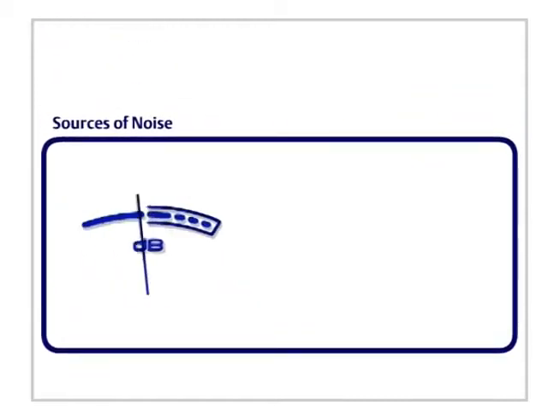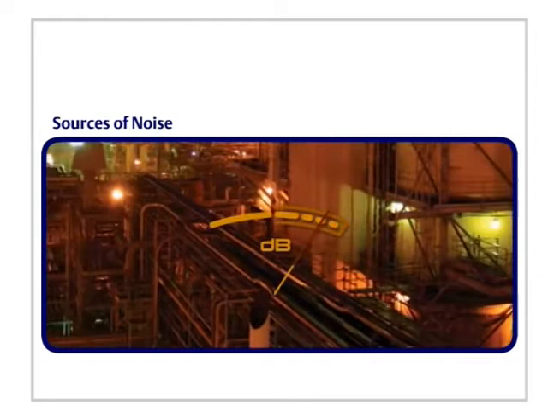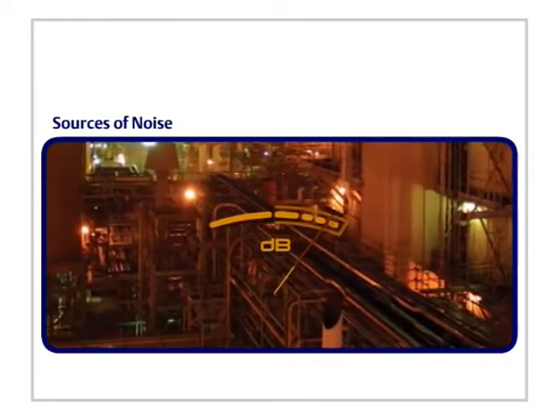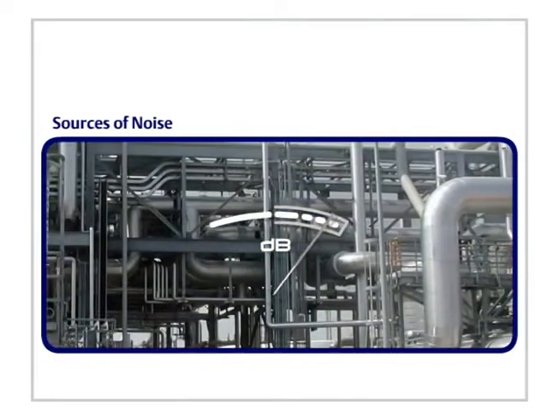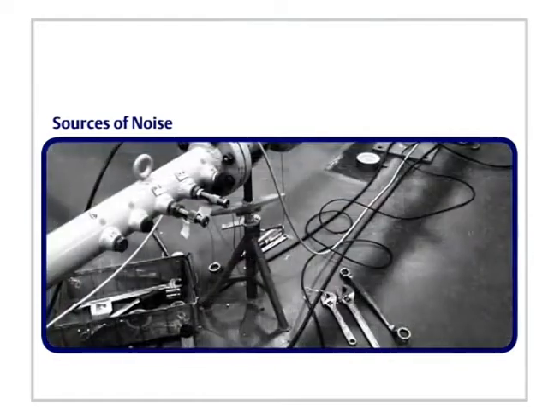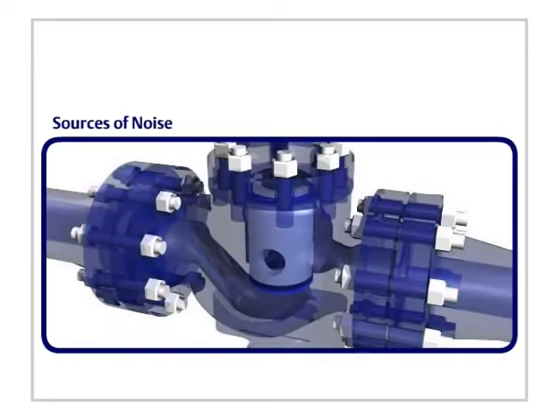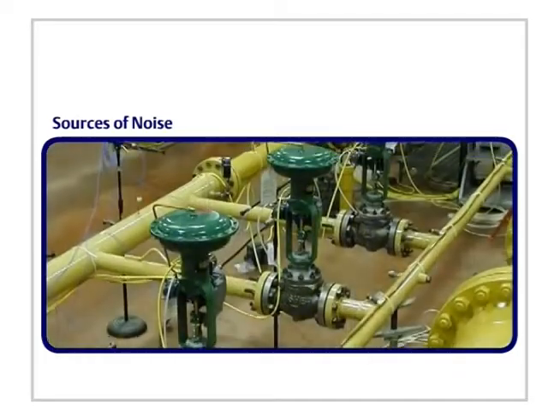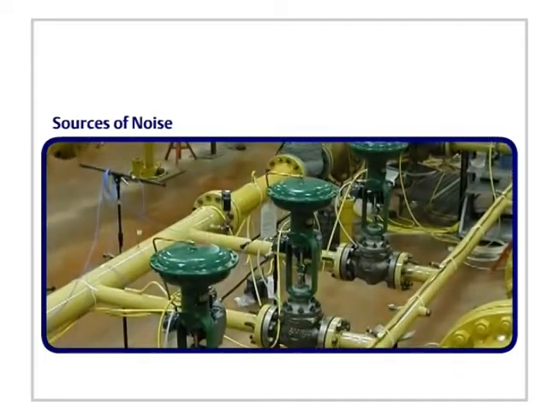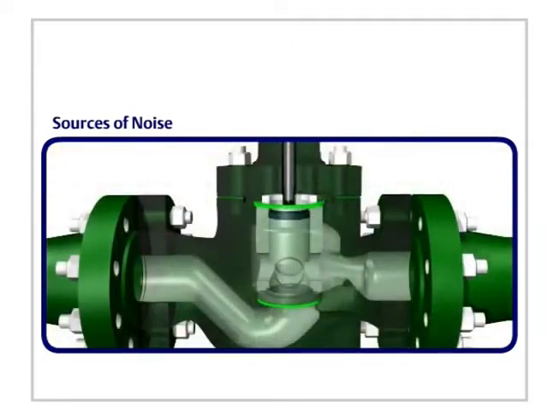Sources of noise. The high noise levels found in severe service applications provide the potential for many risks. Vibration and noise can damage the structures themselves, pose safety risks to workers, or require costly repairs to valves, pipes, other instrumentation, and surrounding equipment. The potential for noise and vibration exists whenever a disturbance in the flow, such as a throttling control valve or change in piping configuration, causes turbulence within a system.